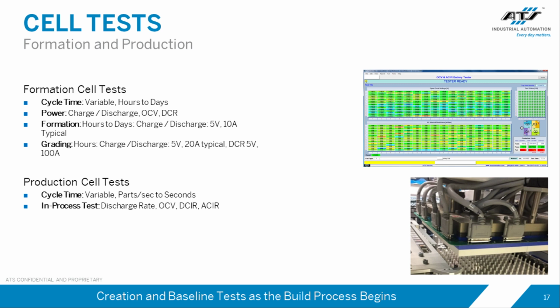Production cell tests tend to be incoming inspection. So now that I've got a bunch of cells, perhaps they came from a different facility, perhaps they came over on a boat, they've been sitting in a warehouse for a month. Finally they come in, I want to make sure they're good. So take those batteries, take an open circuit voltage measurement on them. If you have information on what the voltage was at the time the battery was shipped, lots of times you take the measurement now, do a comparison between the two, and that gives you a real good indication of what the self-discharge is on a battery. Great test if you've got the information.